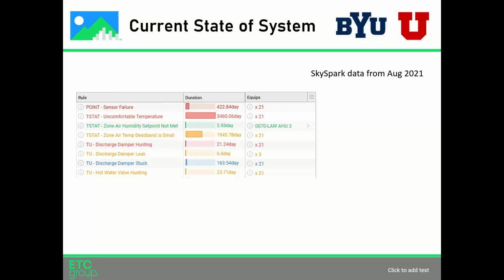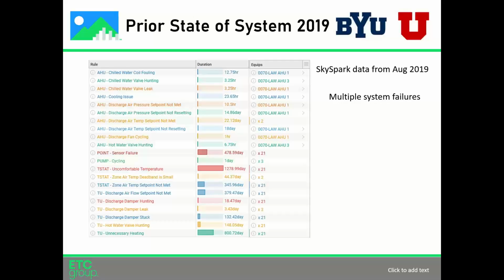As we went further into the process, we went further into the weeds, down the rabbit hole, getting sparks on zone occupancy or thermostats not reporting correctly. We found thermostats in the ceiling or in the wrong room, occupancy sensors wired wrong, frankly a lot of little mistakes compounding our issue. One way I describe it is a cascade of problems, a pile of problems that makes it difficult to resolve the actual big problem.